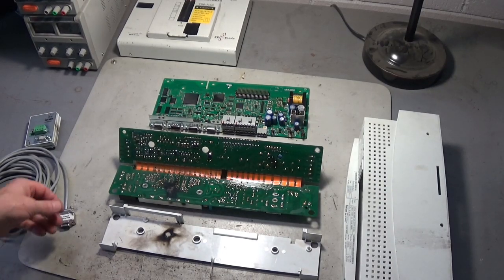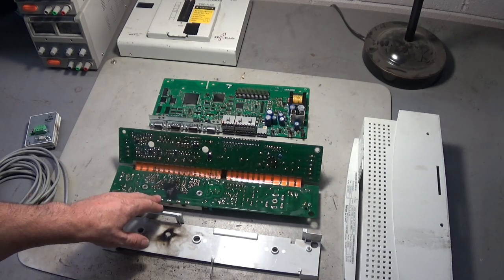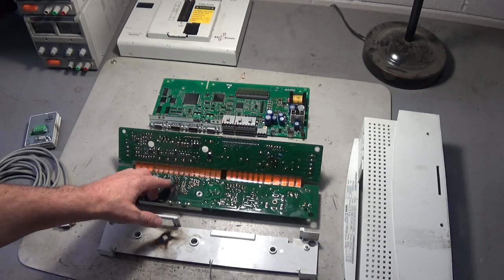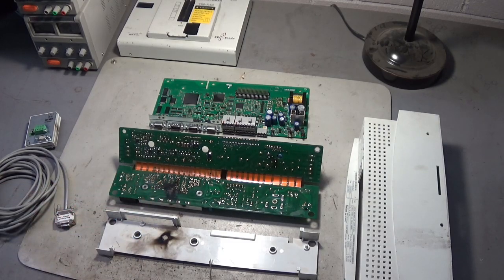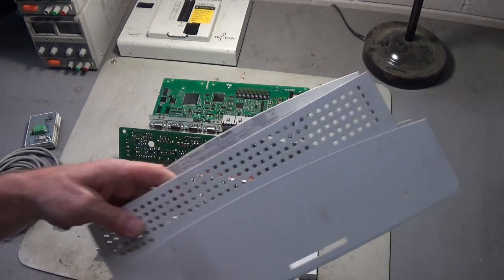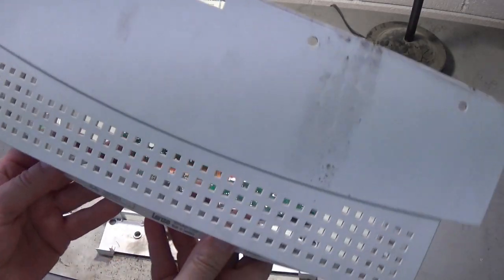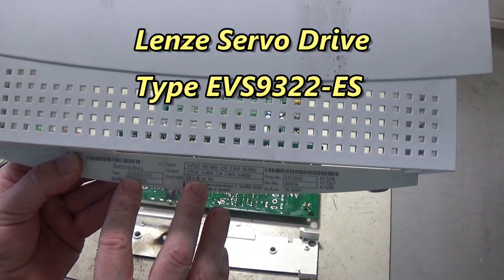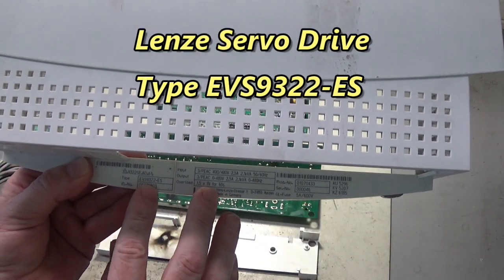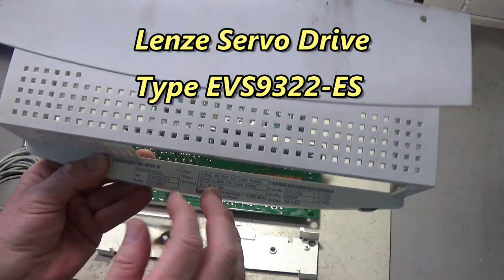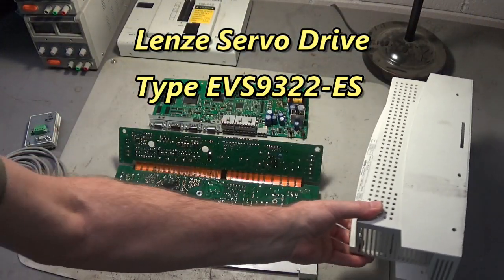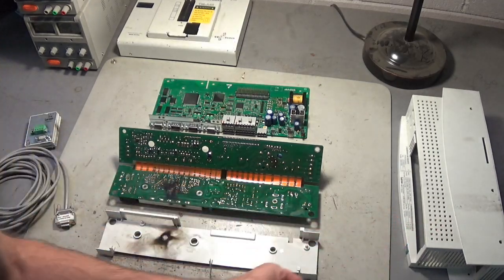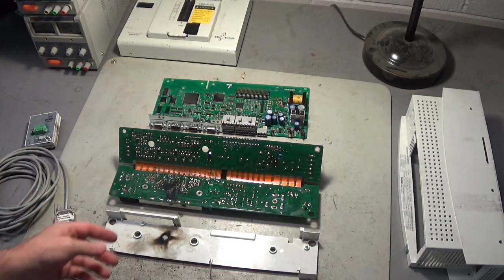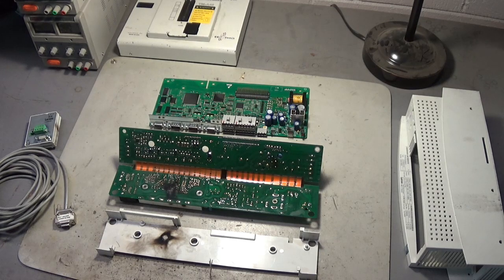Afternoon, all. We've got a blown up Lenze drive, and we ain't gonna be able to fix this. That firing channel right there is smoked. Now this Lenze drive is model EVS9322-ES. And we're gonna buy a new one to replace this blown drive. IGBT shorted out and shot back up through the gate firing channels.